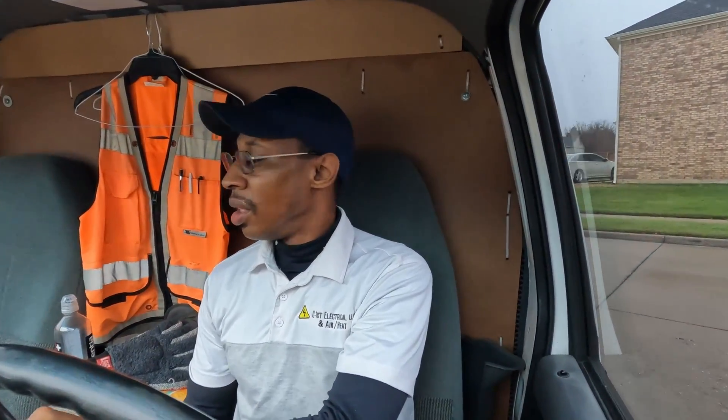Welcome back to United Tradesman Academy. Hey guys, we got a call out this morning that a homeowner's circuit breaker is either tripping or it won't reset. She said it controls the upstairs bedroom or bedrooms. So it's only going to be a few reasons why that happens, especially for bedrooms. Typically you have an overloaded circuit, especially in the winter when they plug in space heaters throughout the house.